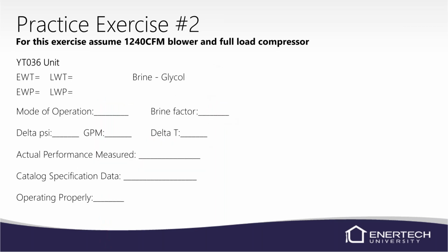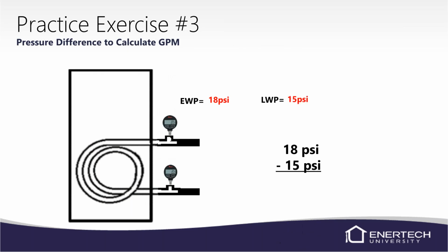So we'll go through and go ahead and do another one here. I think we've got maybe 2 more. This is a 3-ton YT packaged unit at 1240 CFM. And we're using glycol in the system. So we've got entering water pressure 18, leaving at 15. Pretty easy to figure that out. 3-pound pressure drop.